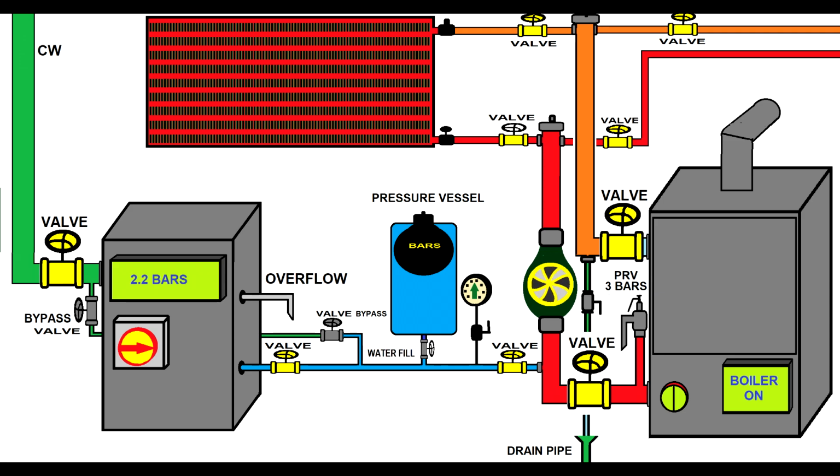up, and you'll see the pressure vessel rubber bellow inside shrink. We all know that when the temperature increases, the heating agent will try to expand, and that pressure vessel will allow a quantity of heating agent to go inside. You just saw that the rubber bellow shrunk, and this is the way the installation works.